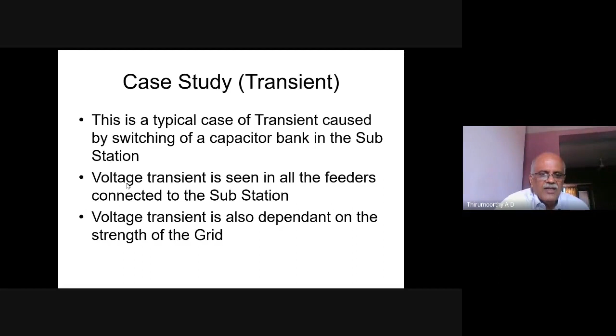So they have started penalizing the generators and consumers for drawing reactive power beyond a certain extent. That led the consumers and also the generators to fix capacitor banks at their facility so that they don't draw reactive power. In the utility also, in substations, to make good a certain amount of reactive power, they have erected capacitor banks. These capacitor banks are switched according to the requirement, and each and every switching of capacitor banks will cause a transient.